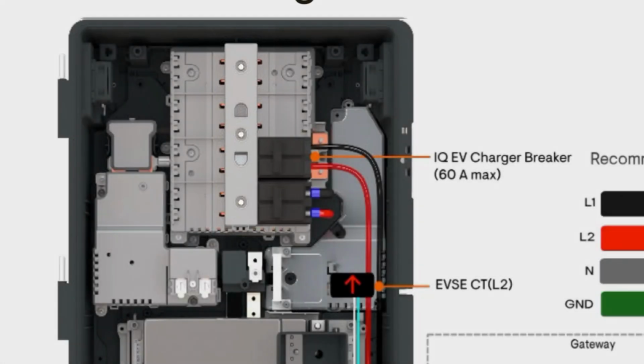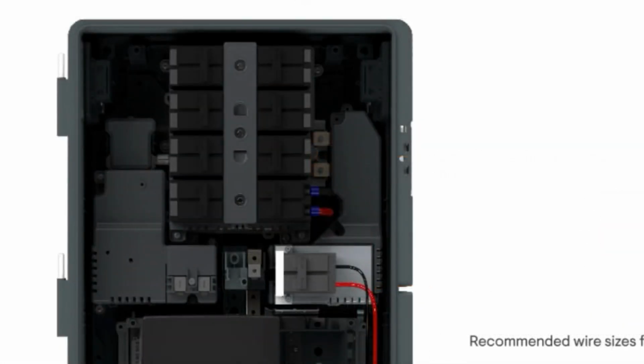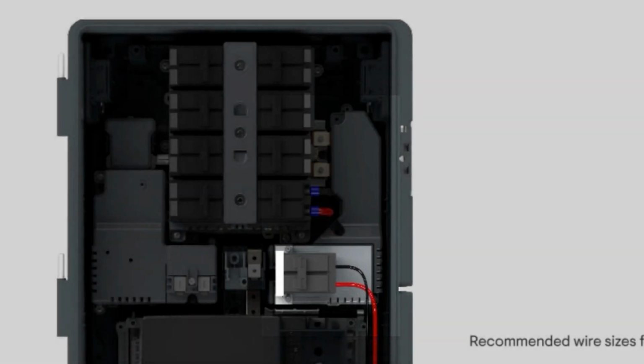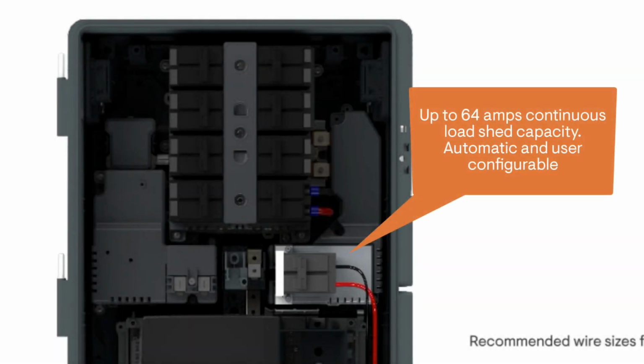408.36D. On the lower right side of the Combiner 6C is an integrated load controller. The load controller contains programming and electrical switching to enable the combiner to intelligently disconnect and reconnect electrical loads. The load controller has a built-in, pre-integrated and wired CT for load metering and a dedicated load control circuit breaker slot for up to 80 amps of overcurrent protection or 64 amps of continuous current.